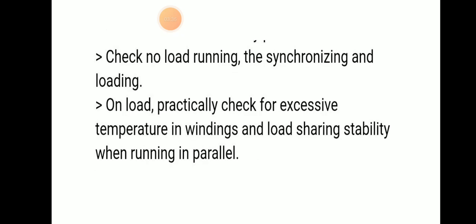And then check no load running and synchronizing of the load. On load, we can practically check for excessive temperature in the winding and load stability when running in parallel.